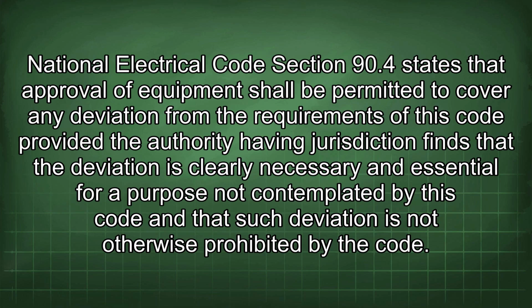National Electrical Code Section 90.4 states that the approval of equipment shall be permitted to cover any deviation from the requirements of this code provided the authority having jurisdiction finds that the deviation is clearly necessary and essential for a purpose not contemplated by this code and that such deviation is not otherwise prohibited by the code.